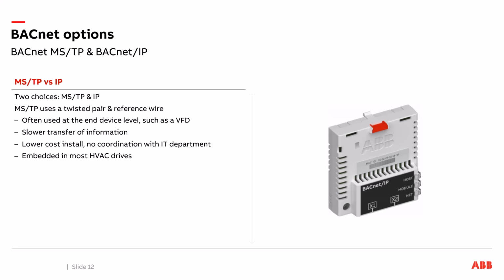So that's why you'll see MSTP, that twisted pair and a reference wire, and most likely it should be shielded, as the typical wiring for your end devices, your components at the very end closest to the application. In the case of drives, BACnet MSTP is embedded in pretty much any HVAC VFD out there.